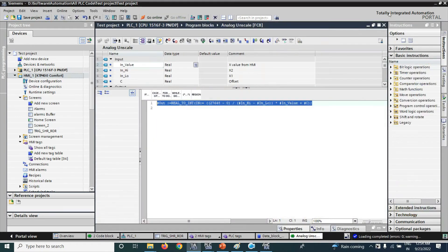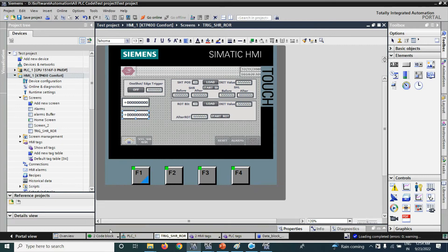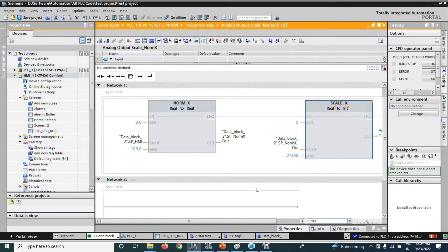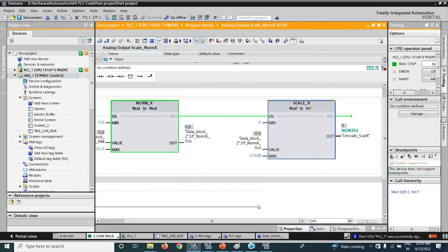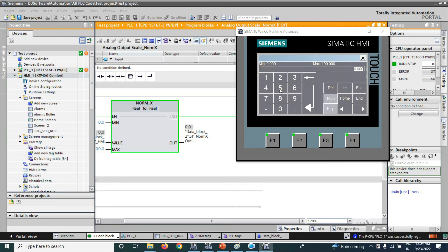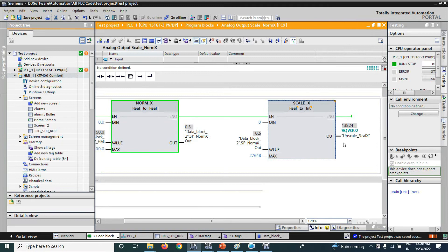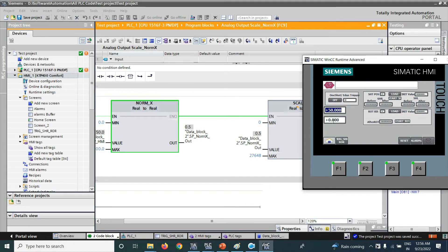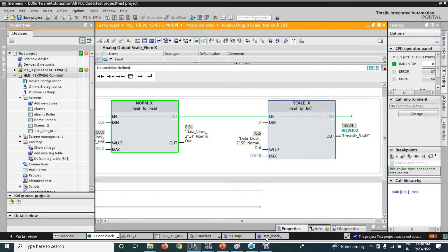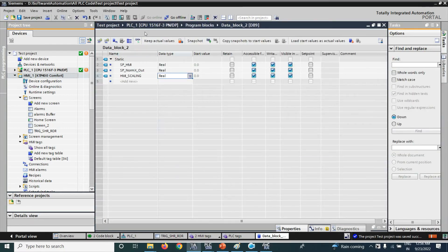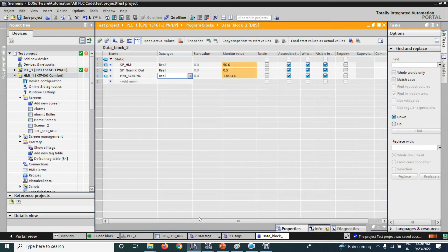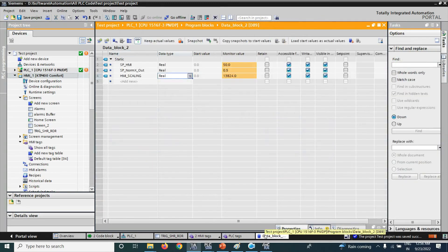Now, as you can see, we already use that one, NORM_X and SCALE_X function here. If I set the value here is 50%, we can see here that is also 13824 is my scaling function. And similar with the NORM_X and SCALE_X function scaling here.